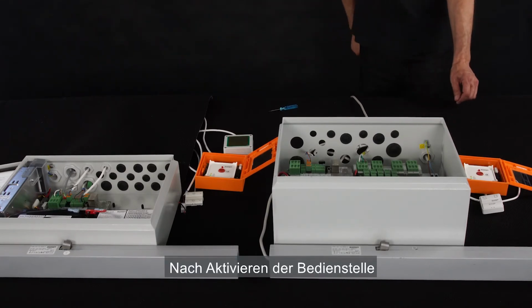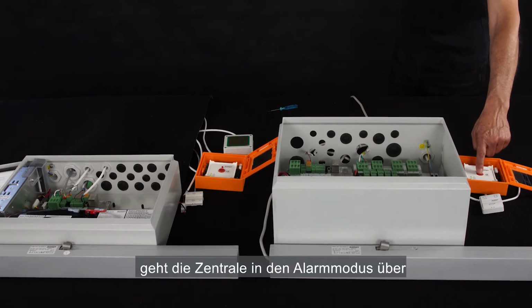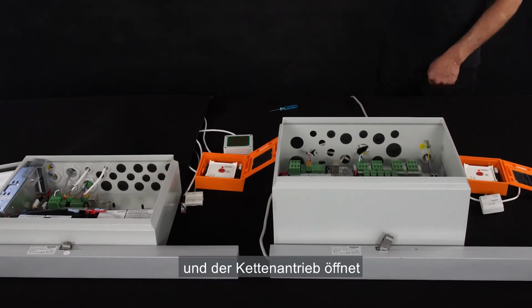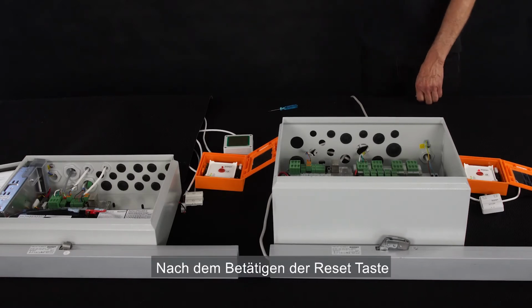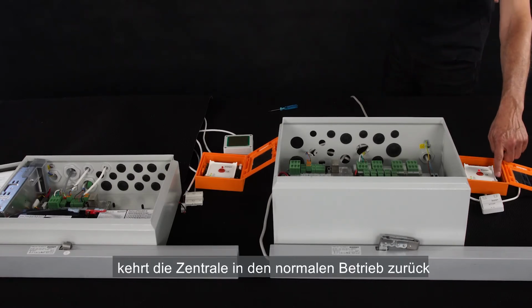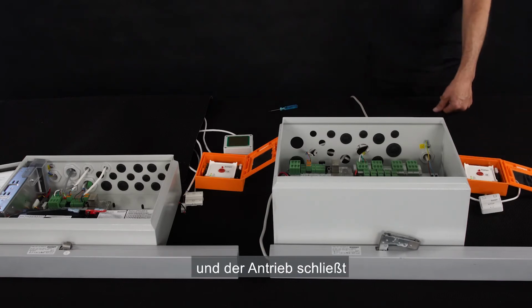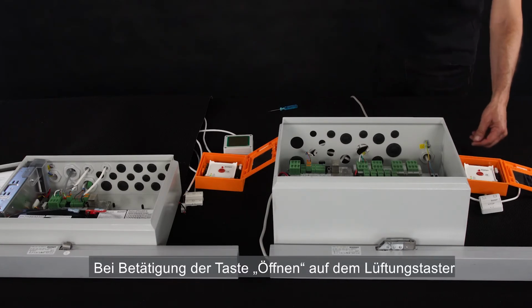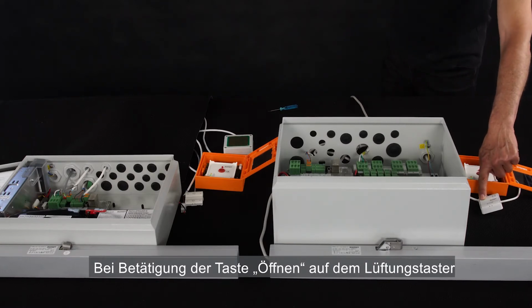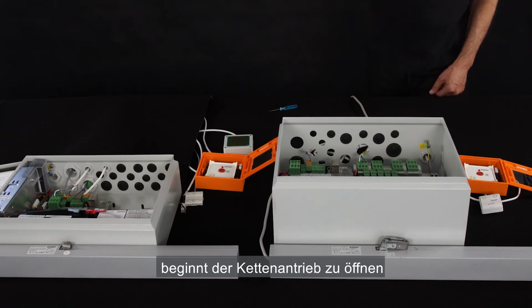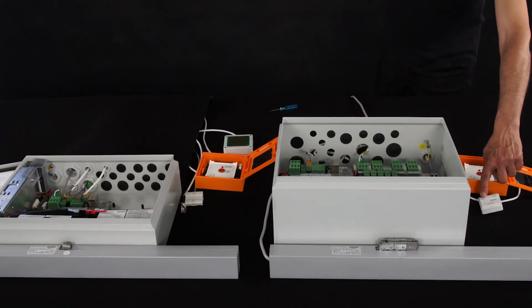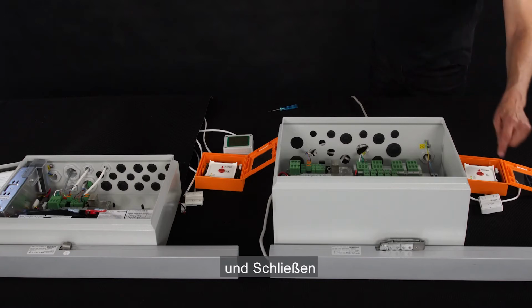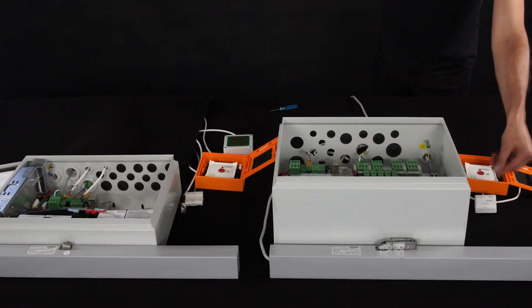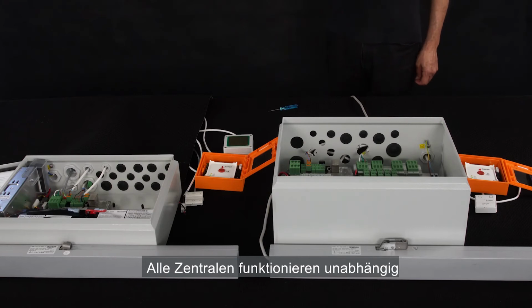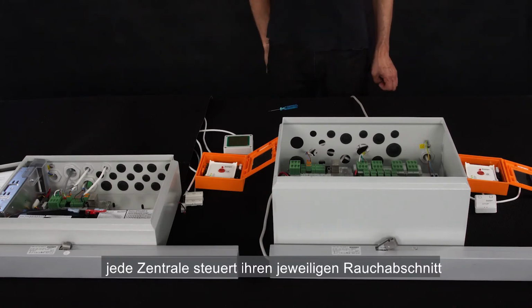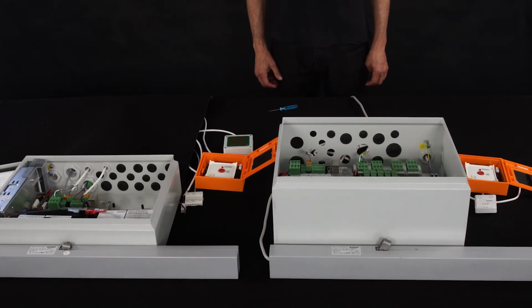Panel 2. If I activate the break glass unit, the panel enters alarm mode and the actuator opens. I press reset, the panel goes back to normal mode and the actuator is closing. If I press the open button on the manual override switch, the actuator is opening. Stop and close. Each of the panels is working independently. Each panel is controlling an individual smoke zone.